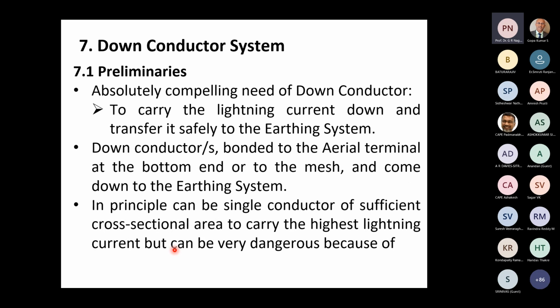Now, having discussed the air terminal system at fairly good length, we come to the down conductor system. I would mention at this juncture that the total lightning protection system for a building consists of three components, as I have made out earlier also. The air terminal system, which attracts the lightning to itself. The down conductor system, which takes the current from the air terminals to the earth. And then the earth system, which distributes the current in the earth in a very safe way. That's very important. Of this whole lot, the air terminal is the easiest to design, and the earth system is the next easiest. The down conductor system can be very complex.